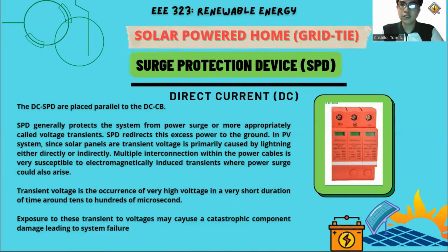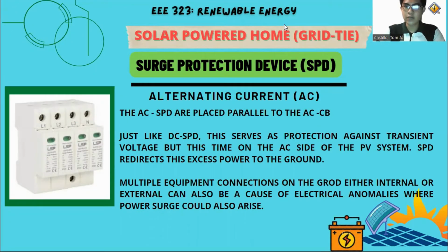So what is transient voltage? Transient voltage is caused by the sudden release of stored energy due to incidents such as lightning strikes, unfiltered electrical equipment, contact bounce, arcing, capacitor banks, or generators being switched on and off. So if there is a DC, there is also an AC surge protection device. So what is the difference between the AC and DC surge protection device? The AC SPD is placed parallel to the AC CB. Just like the DC SPD, this serves as protection against transient voltage, but this time on the AC side of the PV system. SPD redirects this excess power to the ground. Multiple equipment connections on the grid, either internal or external, can also be a cause of electrical anomalies where power surge could also arise.